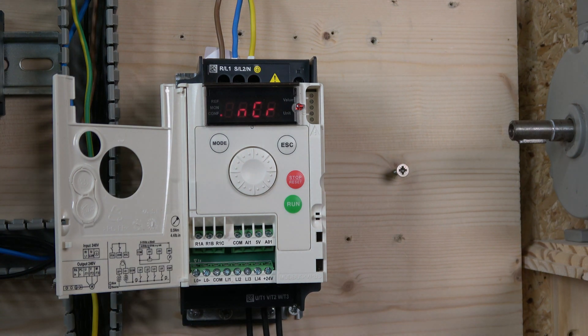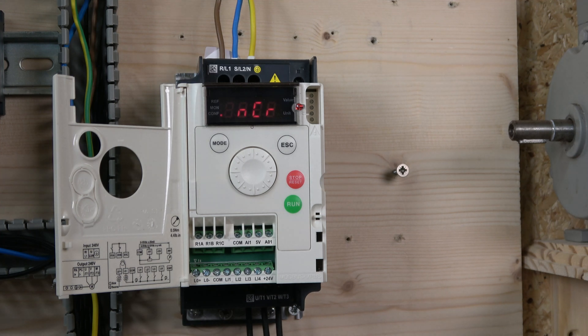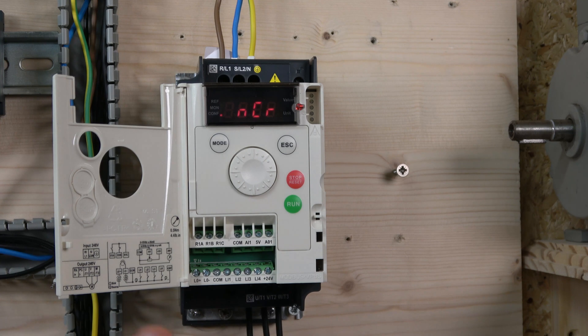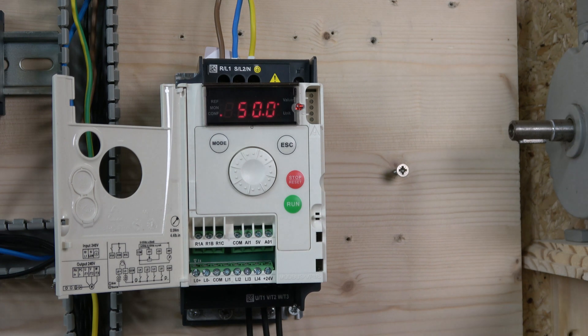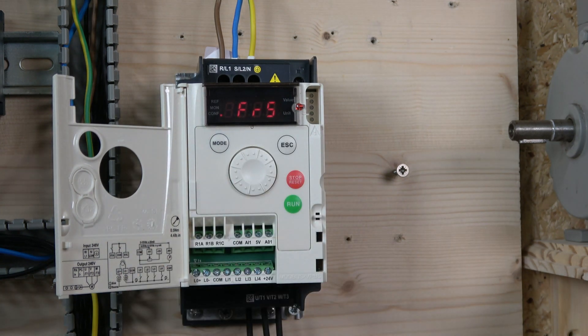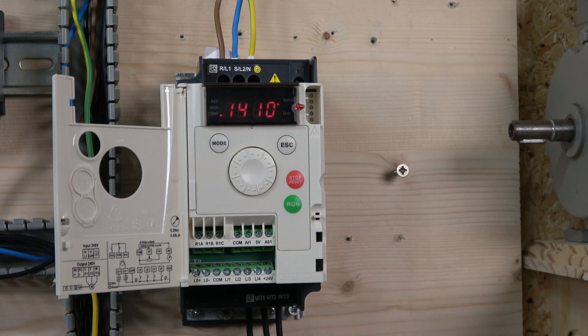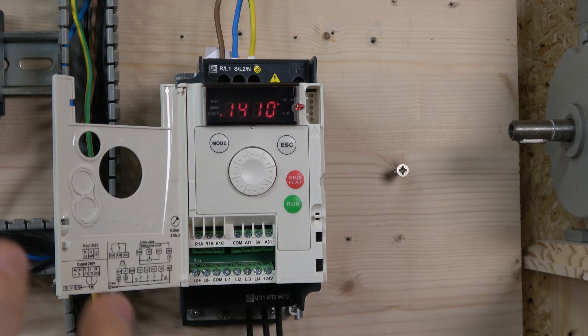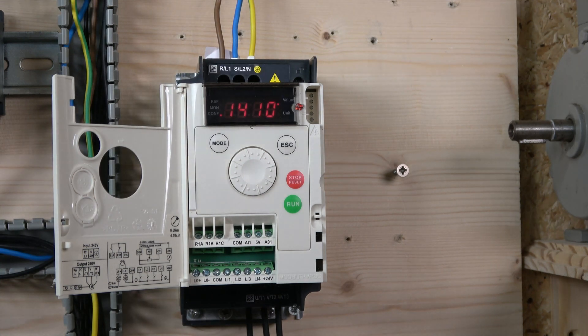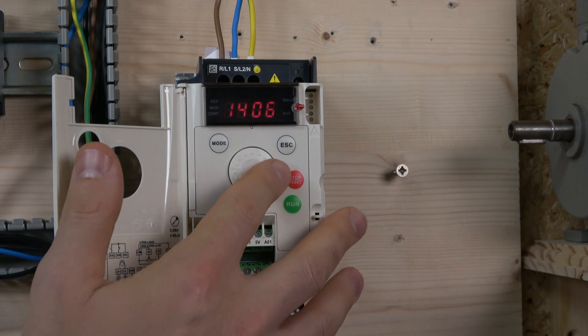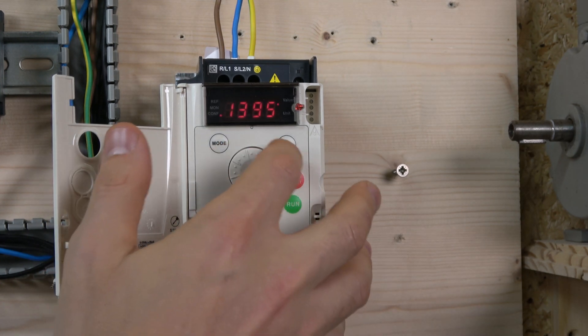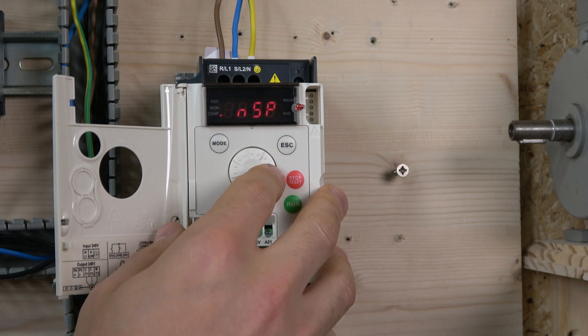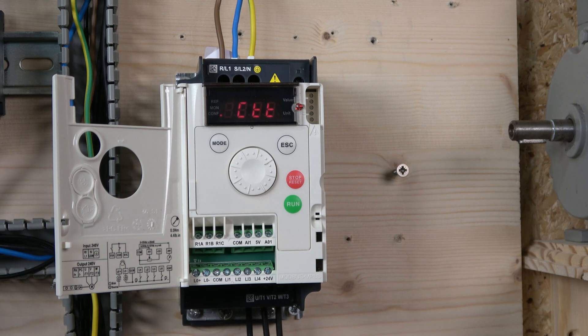Next is FRS, rated motor frequency - up to what frequency we'll run the drive. You can't set this higher than 50 Hertz. My motor is rated at 50, so I'll leave it at 50. Next is motor rated speed - you can set the RPM. Setting this allows the frequency, torque, and auto-tune to be better related to each other. I like to put that. My motor is 1395 RPM, so I'll enter 1395.